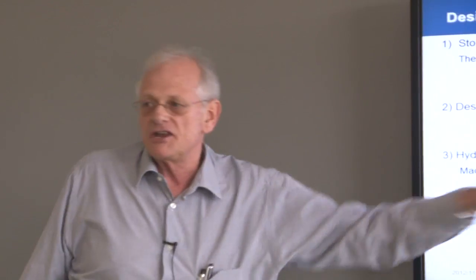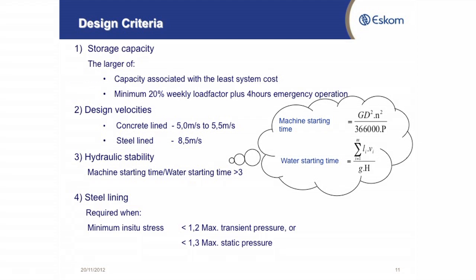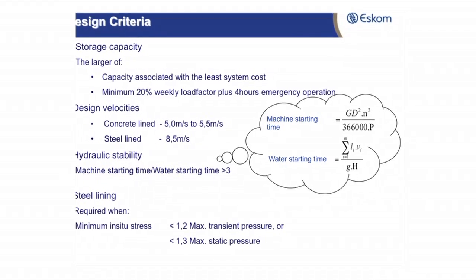this ratio, machine starting time over water starting time, we used more than 3, we were conservative. Some people used 2.5. And there are some formulas for that. But you can work it out from first principles, what that means. Basically, machine starting time is if I have the full pressure of water pressure against the machine, and you open the guide vanes, how long will it take to spool up the machine to the rated speed?